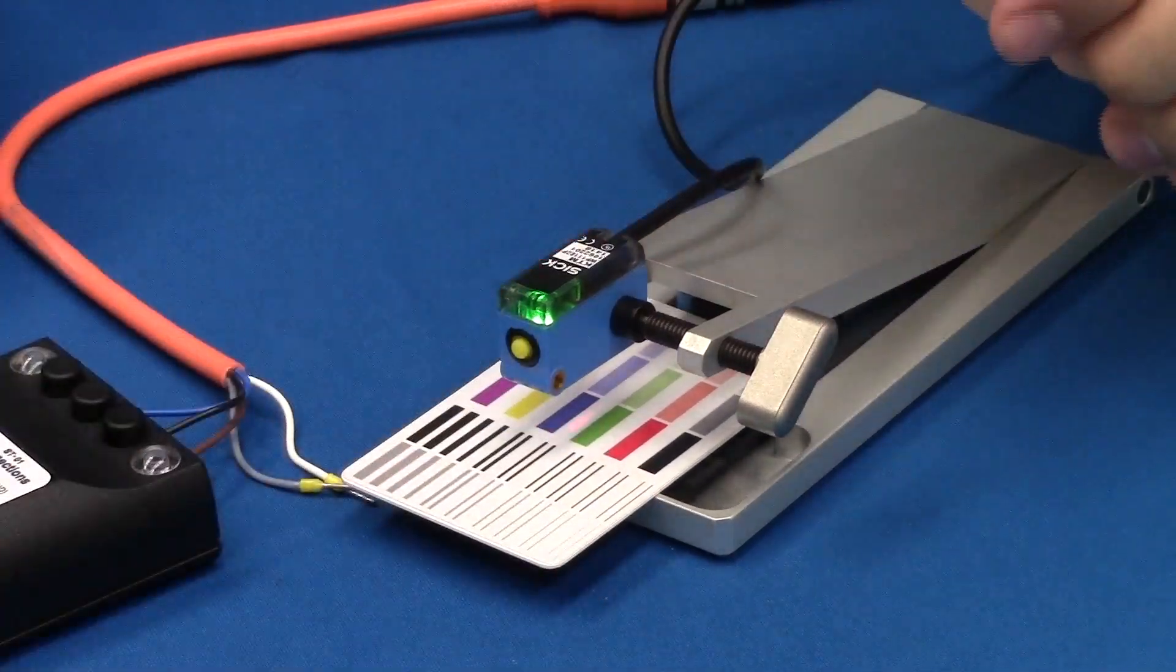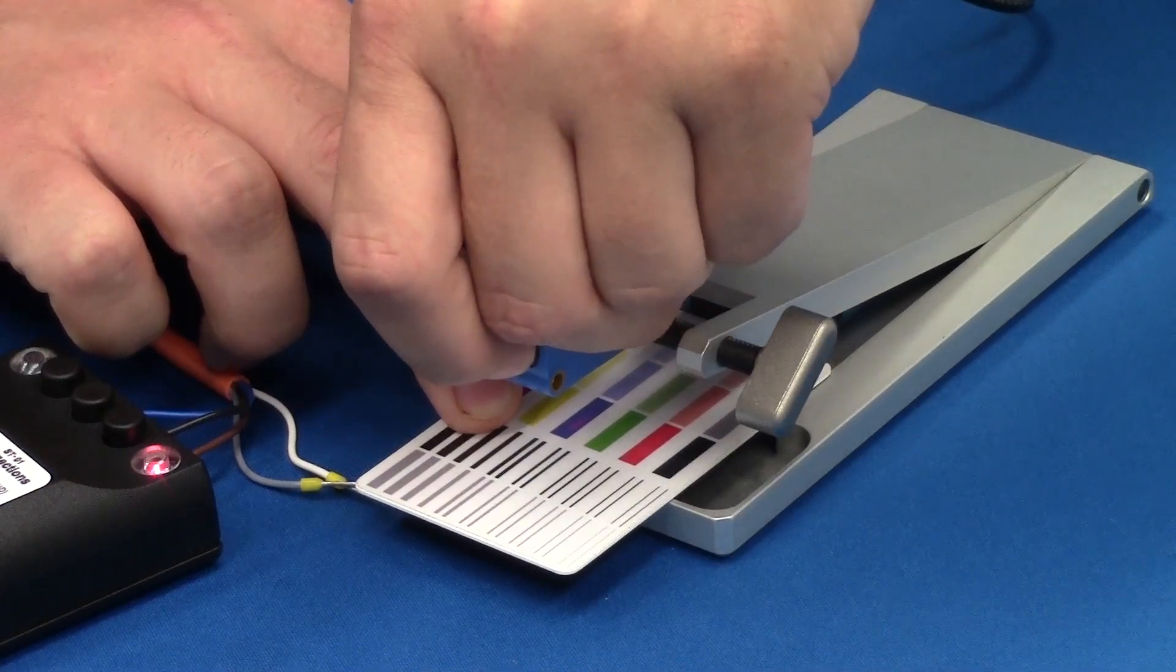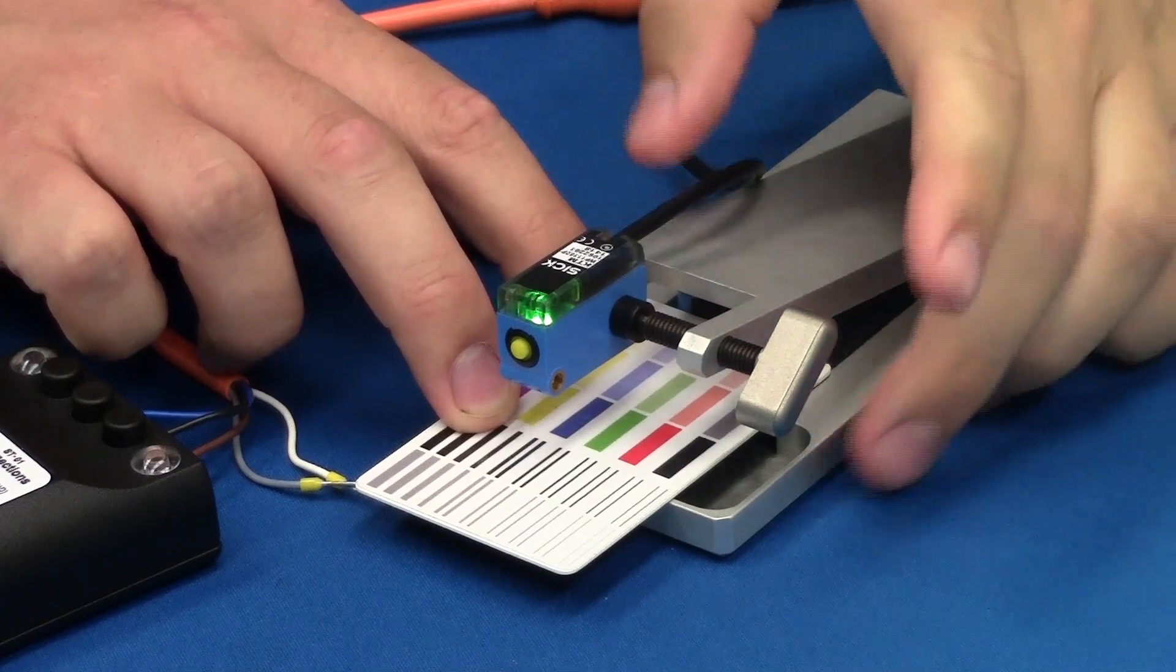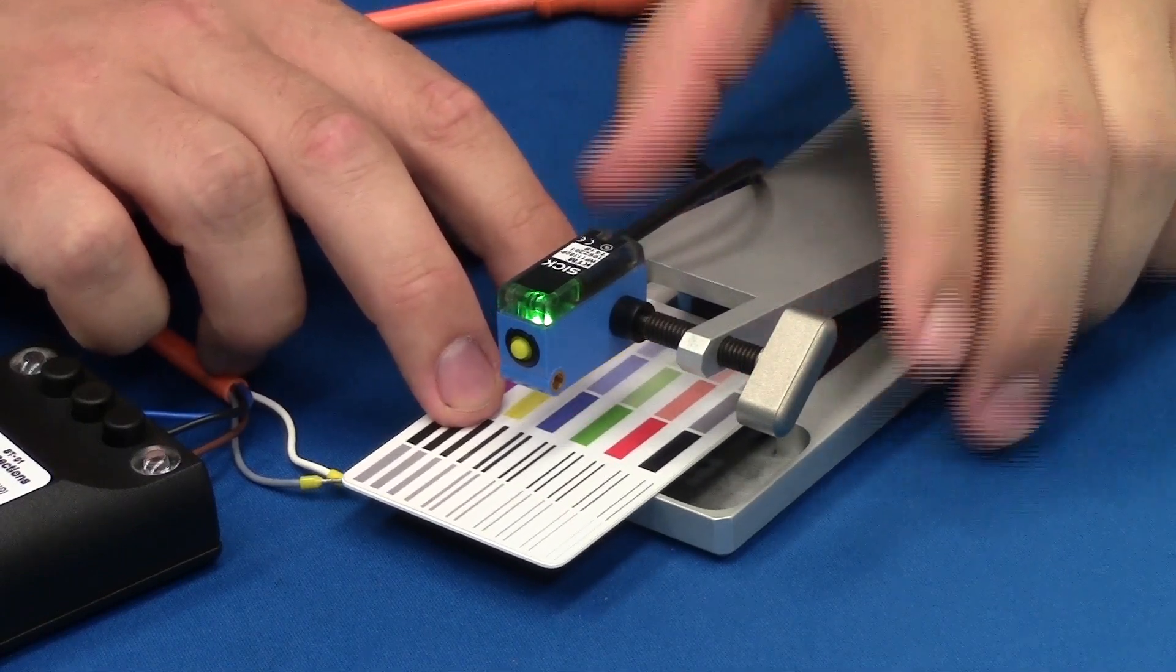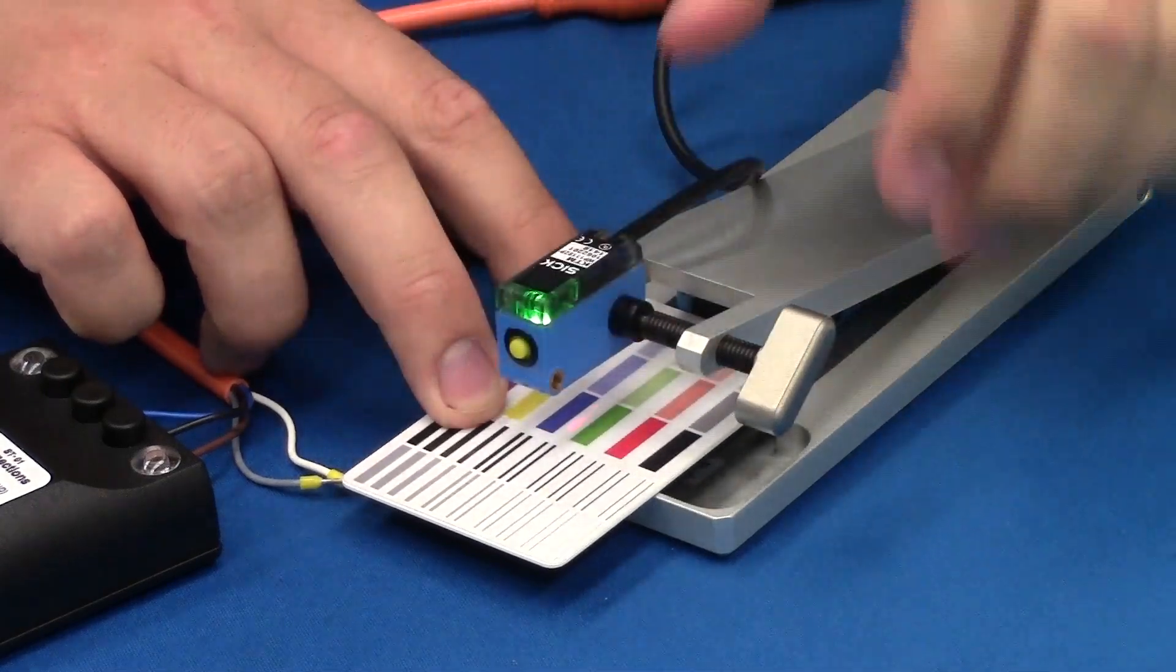Now let's start by demonstrating the static teach mode. To statically teach the KTM sensor, first we move to the contrast mark that we want to see. We push and hold the teach button for one second. Then we have the LED flashing slowly to show that it's in teach mode. We then move to the background and push the teach button once again.